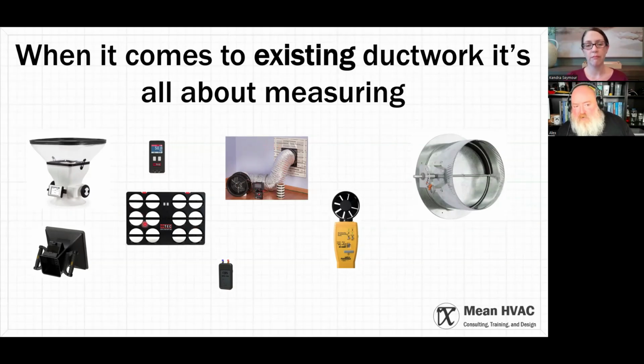There are more accurate tools. If this is a $50 piece of kit, there's about $2,000 worth of stuff here that can tell me exactly, precisely how much air is moving through that system, whether or not the coil is dirty, whether or not the blower is dirty—it just tells me. I could also measure airflow at each outlet. This might cost the contractor $400 or $500. This one, another $2,000.